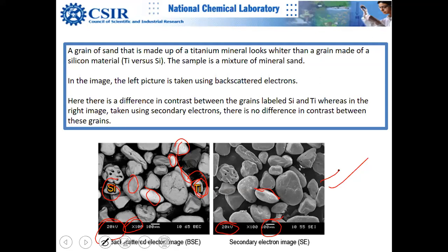So if the number of electrons falling onto the sample is more than the number of electrons exiting the sample, either secondary electrons or backscatter electrons, then you will have net accumulation of charges, and that negative charge which has piled up on your sample will pose Coulombian repulsion from fresh electrons which are trying to escape from your sample.